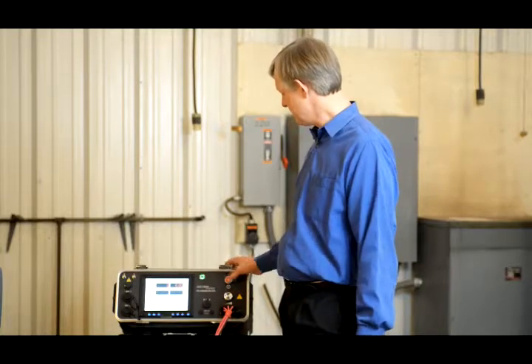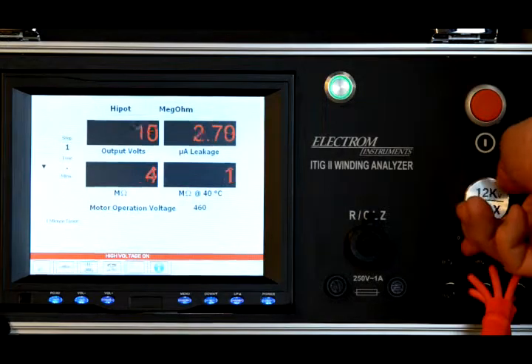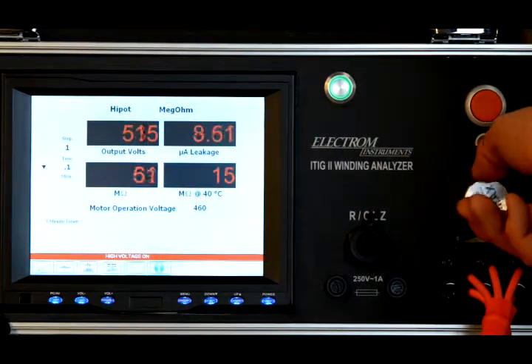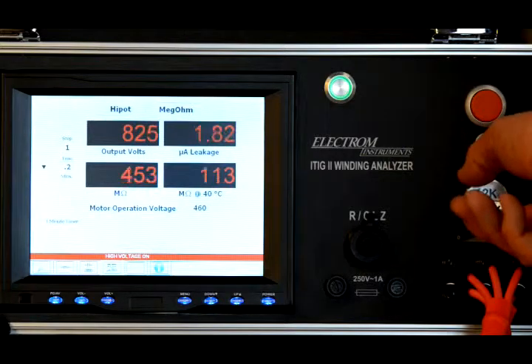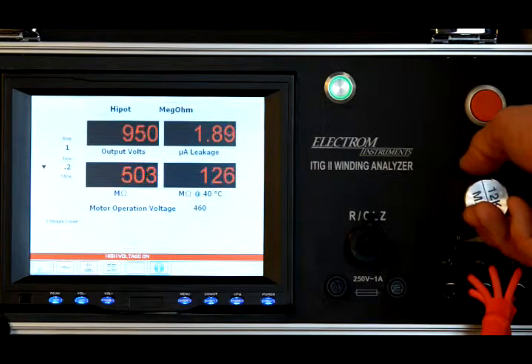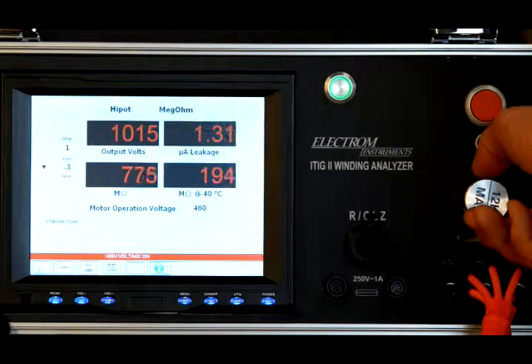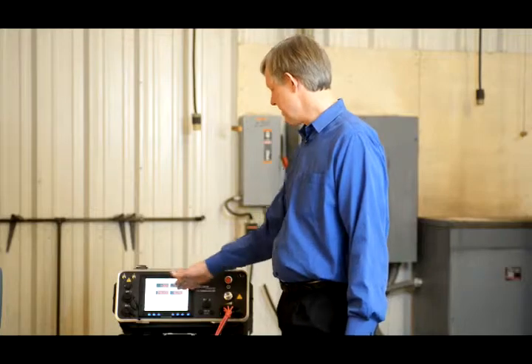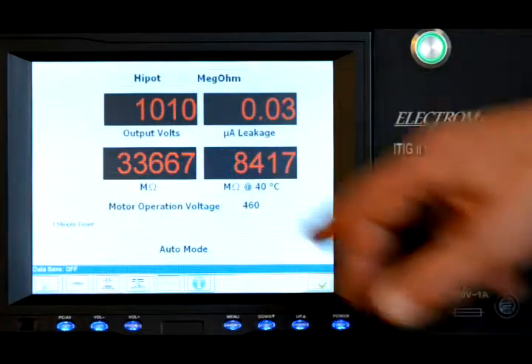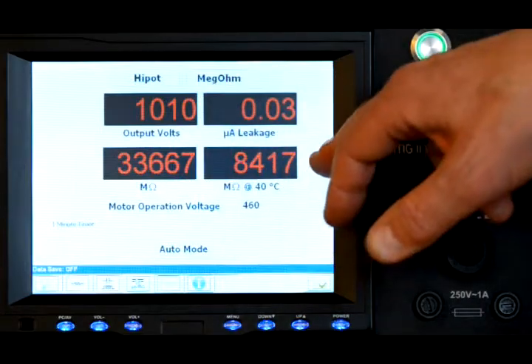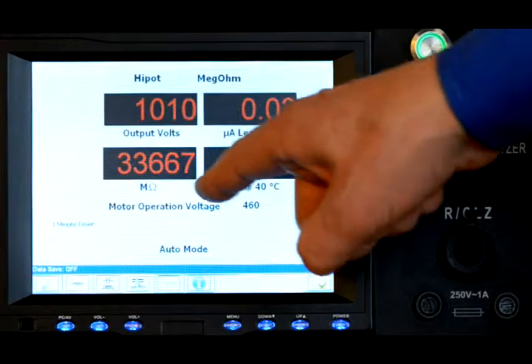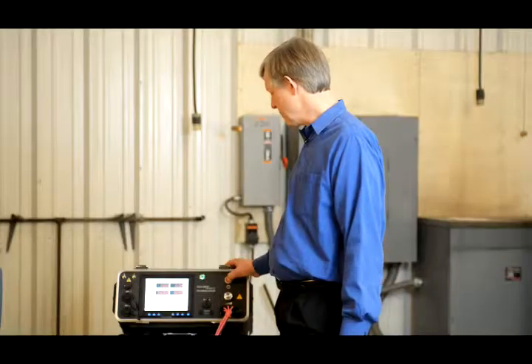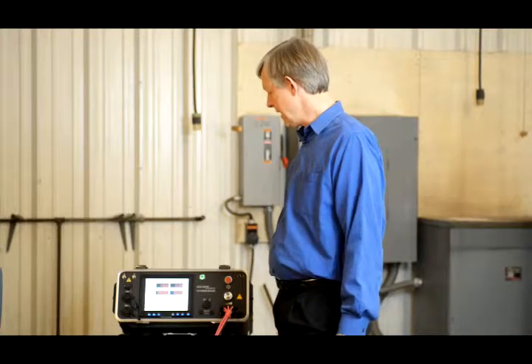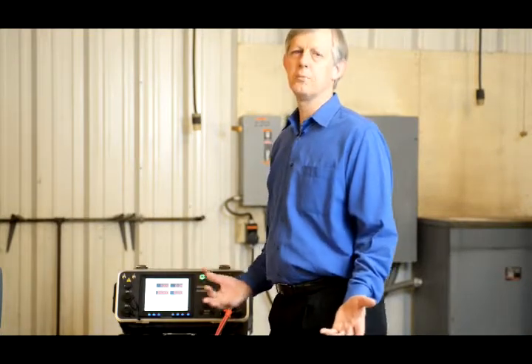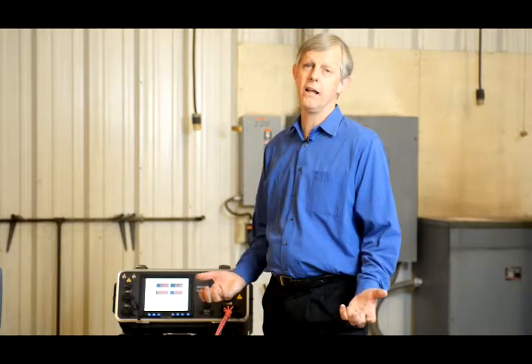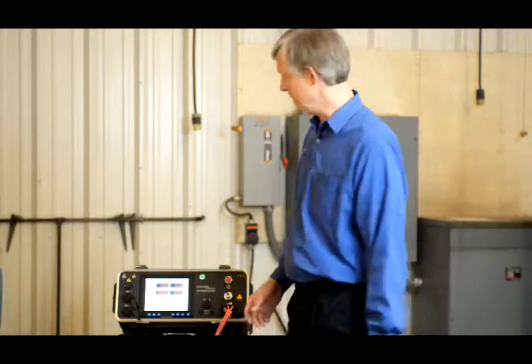We simply press the start-stop button and dial up the voltage to 1000 volts, which is a very common voltage to use. Can also use maybe 500 for a 460 volt motor like this. This is a pretty good motor. It has very low leakage. We have the result here calculated at 40 degrees centigrade, as well as the absolute number, which is over in this display. When we're done, we just press the button again and the test is finished. Normally a megohm test per the standard is supposed to be done or held for a minute, but we are going to shortcut it here.